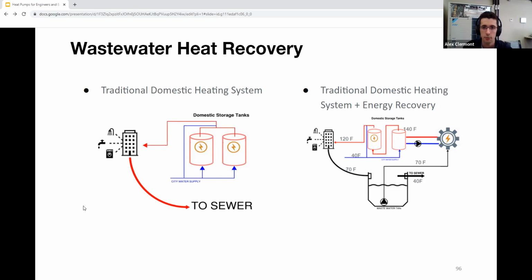On the left, we're seeing a schematic for a traditional domestic hot water heating system. You have city water that's typically around 40 degrees, and it needs to be warmed up to about 140 degrees and held in storage tanks. When somebody in the building turns on a shower or faucet, hot water is sent from a hot water tank to the building. 140 degrees is a little bit too hot for domestic hot water, so it gets mixed with city water to cool it down to around 120 degrees Fahrenheit.